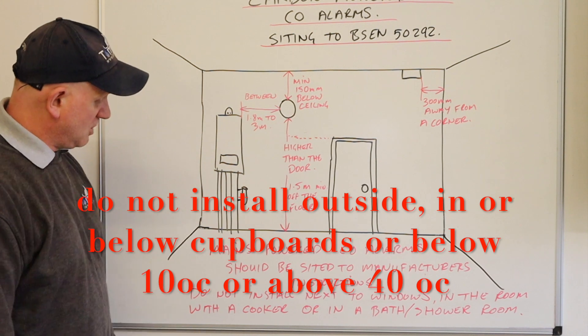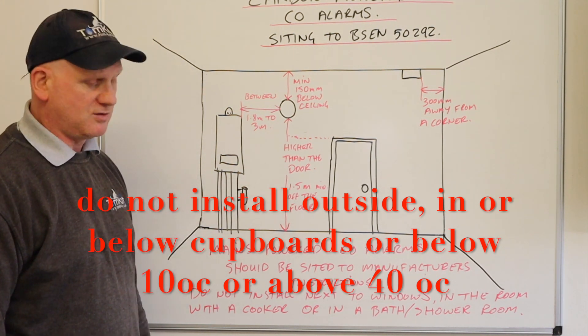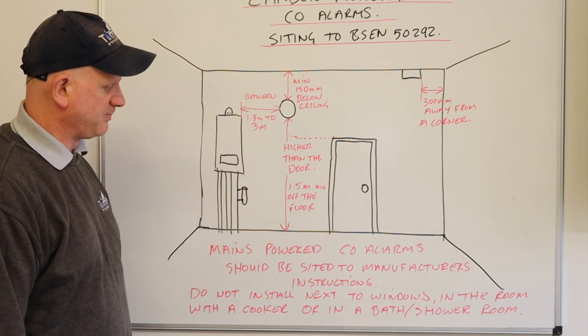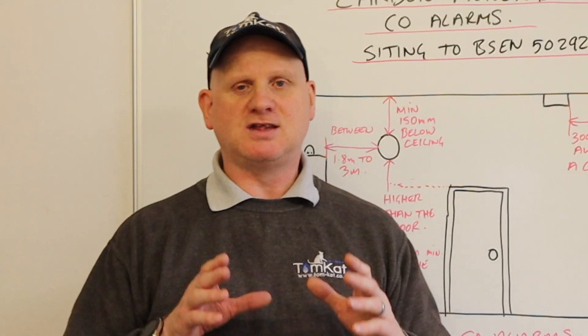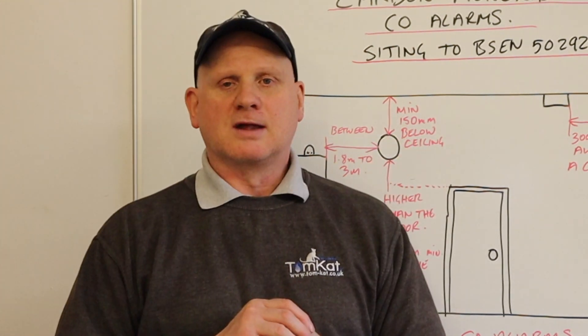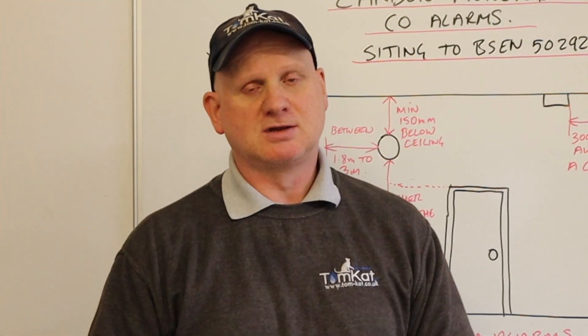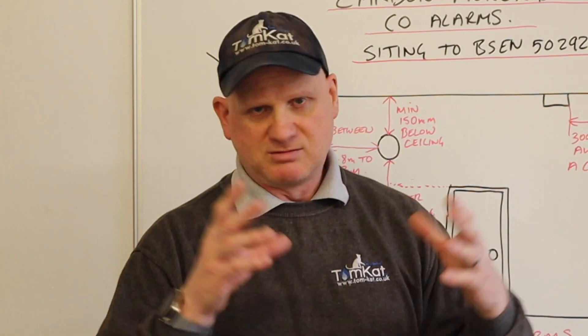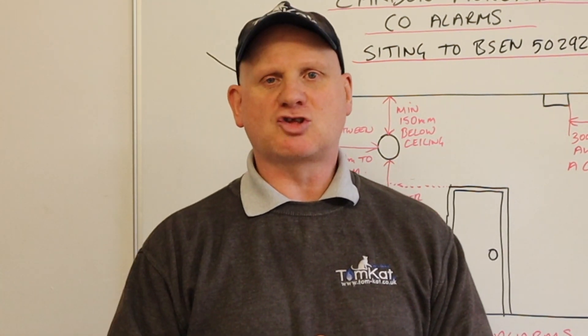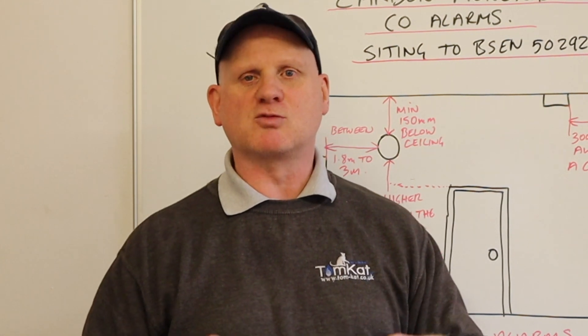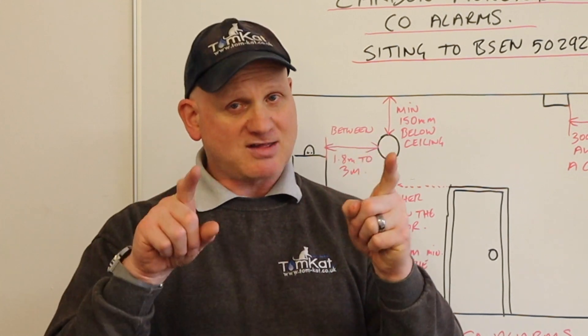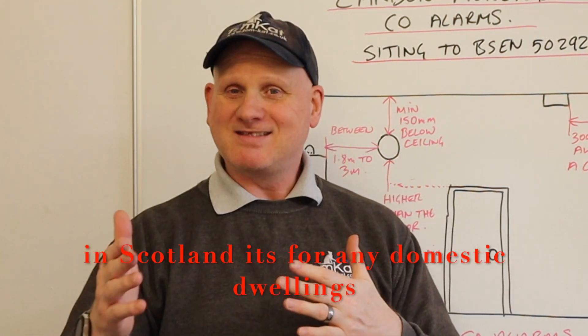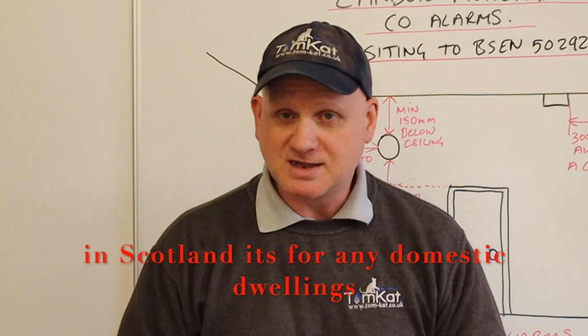Do not install CO alarms next to windows, in a room with a cooker, or in a bath or shower room. Regulations are changing in England for alarms in rented accommodation — they are trying to make it mandatory that whether it's a private or council-run property, CO alarms must be installed, and they will be the property of the landlord who must maintain them. That's already been in place in Scotland for a very long time, and hopefully by the end of this year they'll be bringing it in for England.